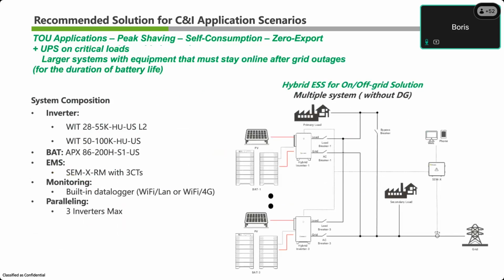This is just showing that it's the same exact scenario with the on-grid focus system. If you want to do parallel systems off-grid or on and off-grid, you can do that with this system as well, but you need that SEM-X-RM, and it works exactly the same way. We have a secondary load, primary load, all being backed up, but this has a 3 inverter maximum.